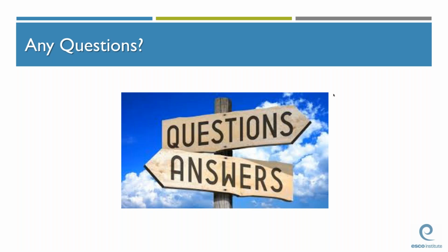We also had a question about EPA, some books saying to use R22 as the trace gas. Yeah, just to hop on that, the EPA never specifically mentioned R22. The industry, not the EPA, the HVAC industry picked R22 because it was a safer refrigerant, but the EPA never specifically mentioned R22 by name. So it was industry accepted that R22 was the trace gas to use, but that was never stated by the EPA.